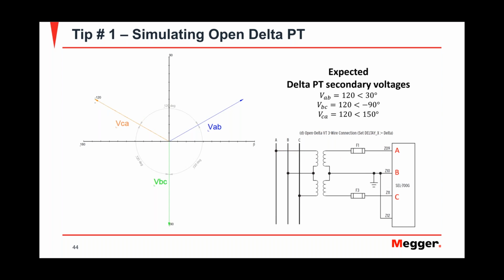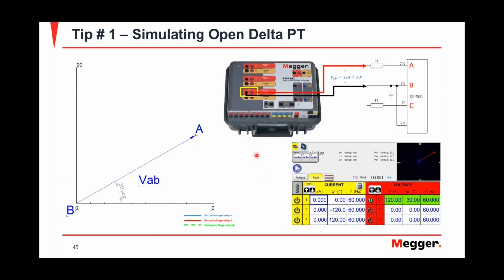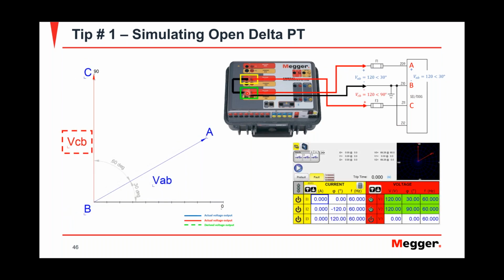So how would you do that with a relay test? First of all, you inject from one channel to A and B. You would connect 120 volts at 30 degrees. That creates this phasor right here. You would set it up on your test set like that, 120 volts, 30 degrees into A and B, and you would wire it like this: your red, your polarity, into A, non-polarity into B. This is what the relay would see. You're injecting 120 at 30 degrees, and your relay will see 120 at 30 degrees, because that's the polarity it wants to see, positive on A, negative on B. The next thing you're going to do is add a jumper on B phase.